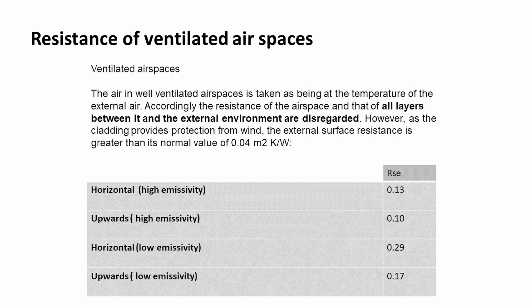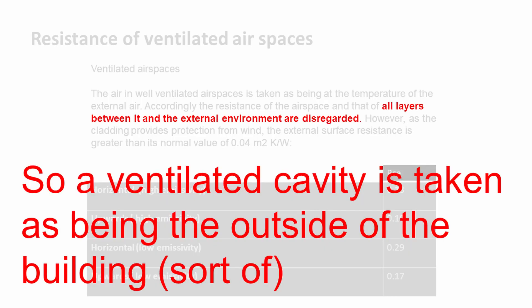There are different resistances for ventilated air spaces. If a design has a cavity within it with horizontal airflow, we would have, depending on the emissivity, a value of 0.13 or 0.29. There is a caveat that all layers between the ventilated airspace and the external environment are disregarded — effectively, a ventilated cavity is taken as being the outside of the building.